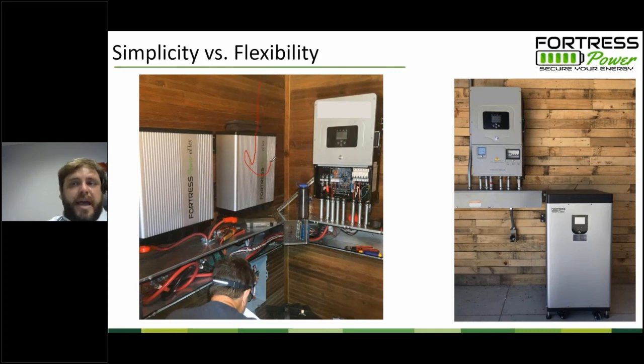Okay, so why would you use the eFlex instead of the eVolt? Here's an example where they wanted to put the batteries on the wall. The eVolt is really too heavy and large to be wall mounted. So maybe you're in a small room or a closet space and you don't have much space to stick out in front of your electrical equipment. You don't have the space for the eVolt to go right off to the side, but you have plenty of wall space. That would be an instance to use the eFlex. The eFlex has a more robust environmental rating. So if you're putting your batteries in a dusty barn or a porch where it's going to get humid, having that extra environmental protection from dust, humidity, and temperature is an advantage of the eFlex. And so you want to spend a little bit more money for that.